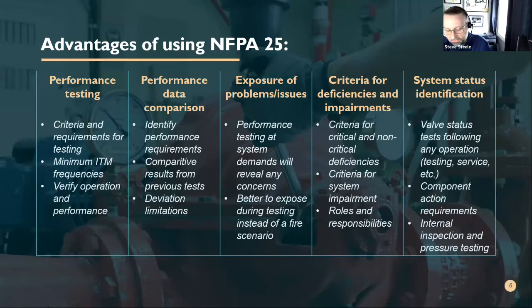So with that comes performance data comparison. So very integral part of NFPA 25. You get those results, you collect the data, but you also do a comparison of the data to previous years and the original acceptance testing or commissioning of that system. You're going to see some deviations to that. You're going to see it degrade over time. That is a natural cause.